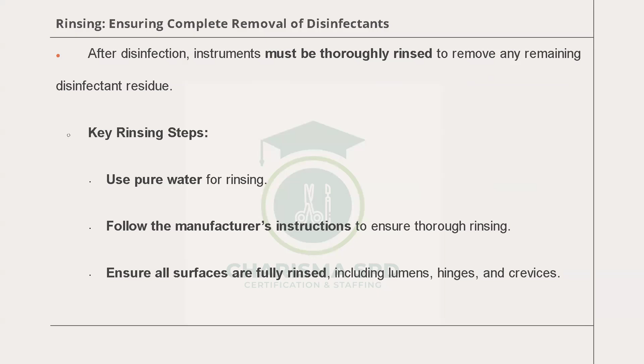Then the lumens. When we say the lumens, we are talking about the internal channels. There is something we call a scope body, but that one is used in the decontamination room to flush. The AER machine also has connectors to the biopsy channel, to the flushing port, and those things, and they are able to flush water through it to make sure that they are thoroughly clean. Yes. Next slide, please.